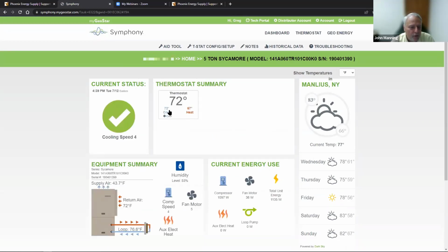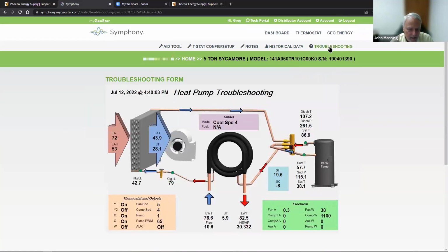And it tells us the cooling set point and the actual temperature in this space. It tells us it's on cooling speed 4. And probably my most go-to screen is the troubleshooting screen. This gives us the schematic of the refrigerant circuit. It gives us all the data points.